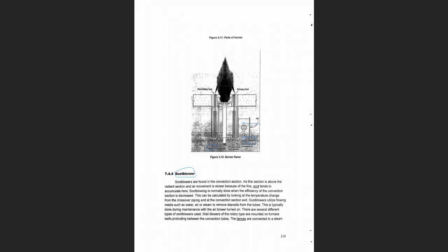Soot is actually a form of ash, okay, and carbon accumulating outside the tubes. اللي هو التراكم اللي هو بعض الأحيان يكون عندك تراكم للرماد وتراكم للكربون الناتج عن عملية الاحتراق غير الكامل على الجدار الخارجي للتيوب. الحين الكوك inside the tube. جميل. Whereas the soot is outside the tube. So soot is actually another form of fouling, but it occurs outside the tube. And it's actually a very big problem in the convection section.